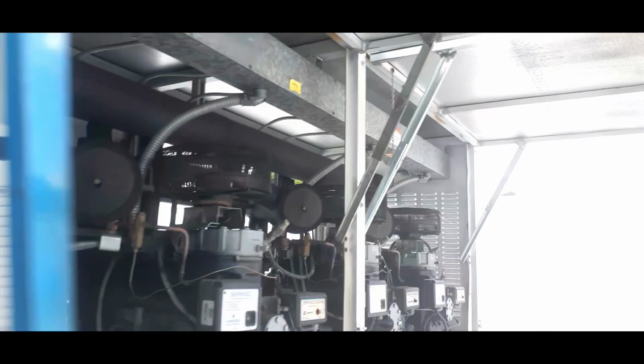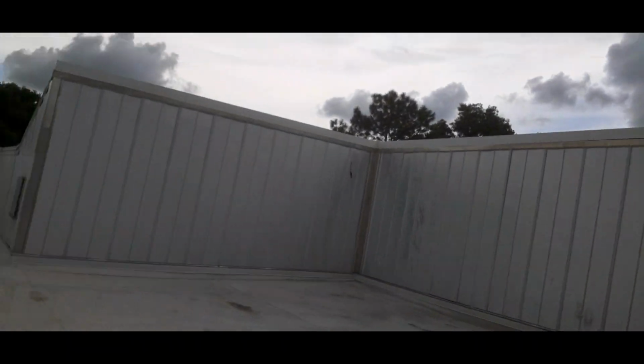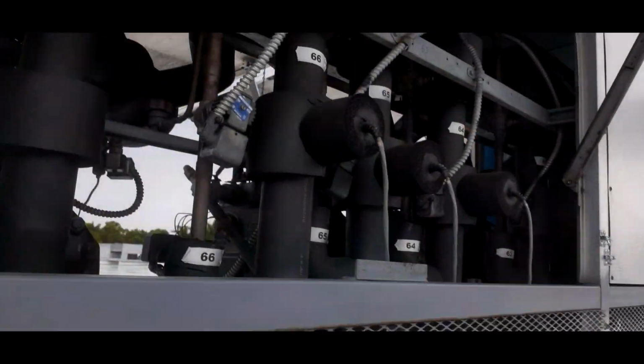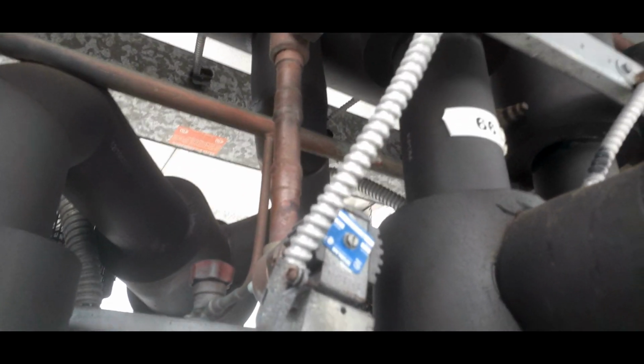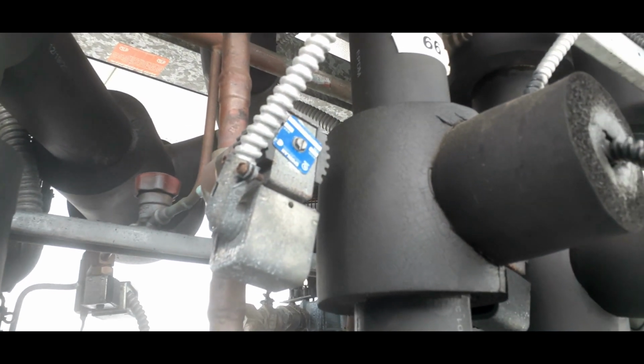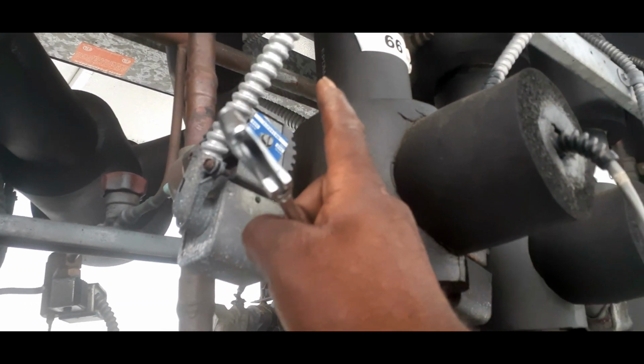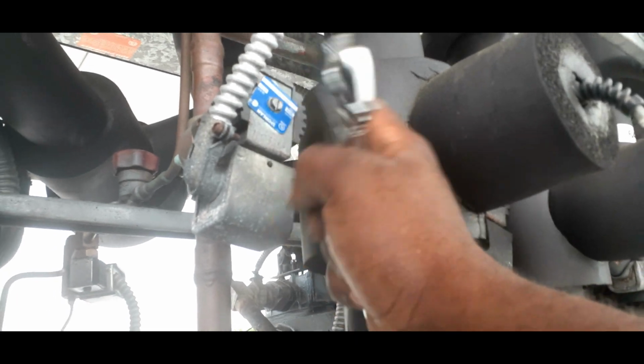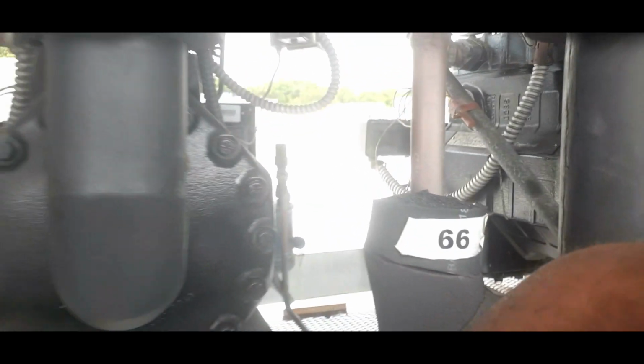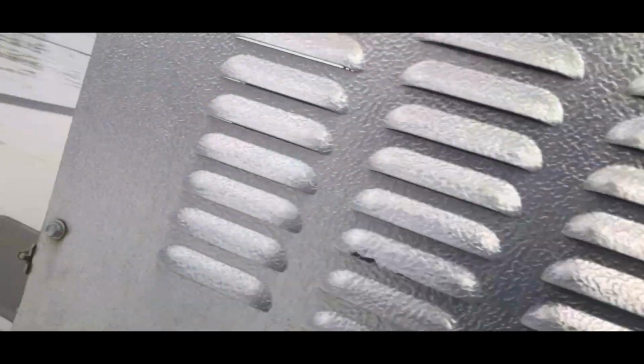Alright, 63 on the rack suction pressure. Let's just close that one circuit down back here and let's see if our suction pressure drops a little. So we're just gonna valve this off. I'm gonna shut this circuit down. Look at that. That noise went away. I don't know if you heard that, but this hot gas solenoid is sticking, washing out the rack, causing the compressors to go off on overload. Could even break a valve plate, piston, anything.